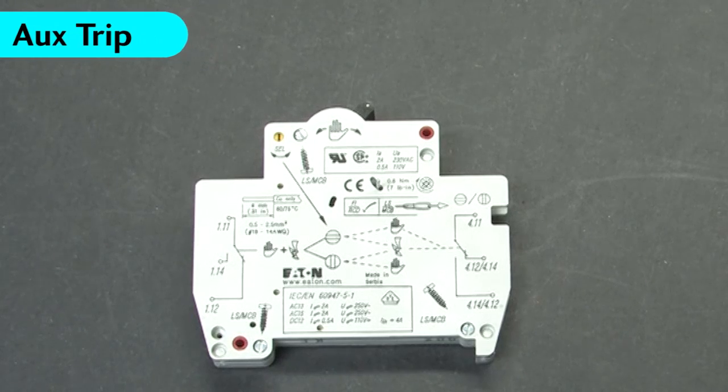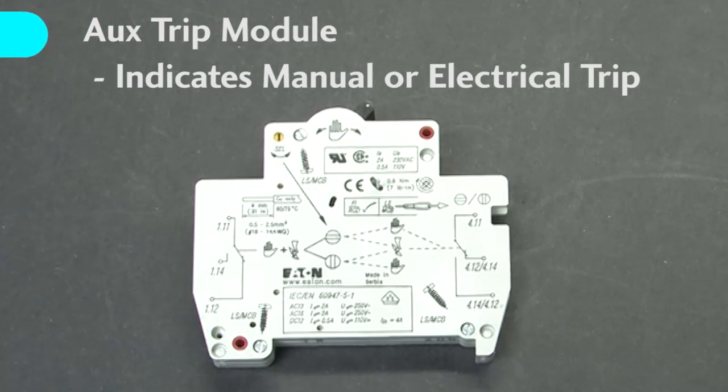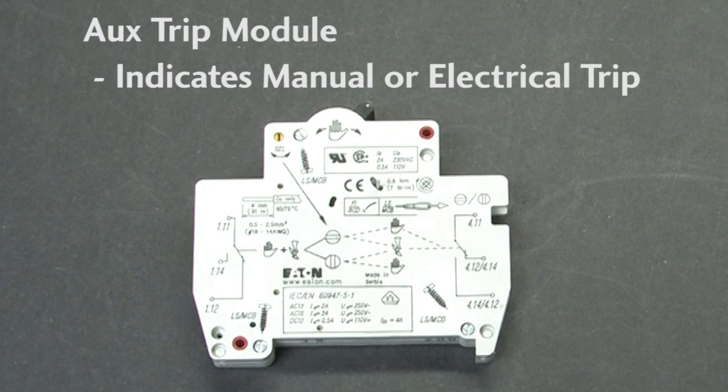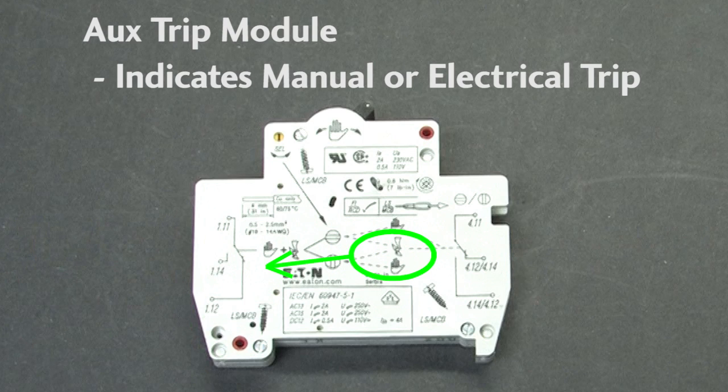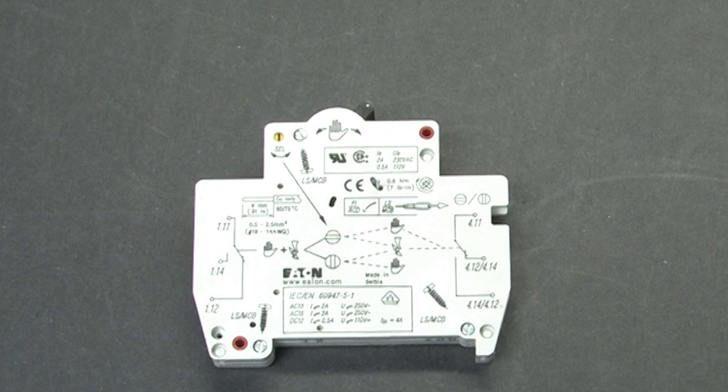This AUX contact is a little different because it can detect if the breaker was tripped manually or electrically. This set of contacts tells you if it was tripped electrically and this set tells you if it was tripped by either. Connect those to PLC inputs and now the PLC can tell what caused the breaker to trip – a fault or a co-worker.